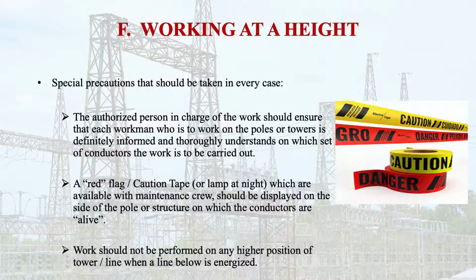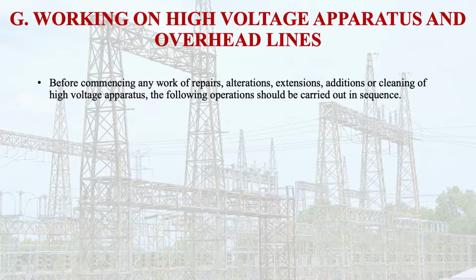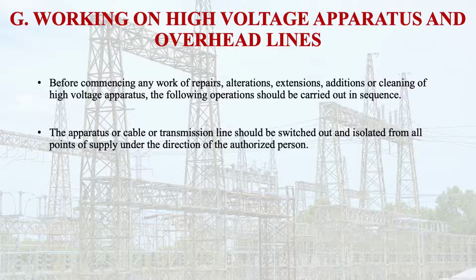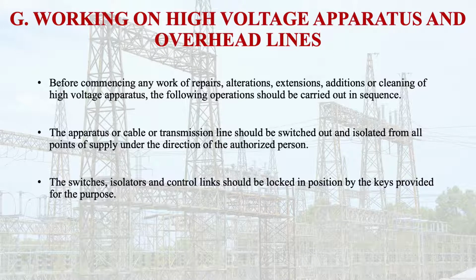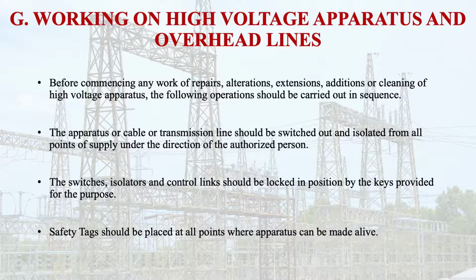Now let us discuss working on high voltage apparatus and overhead lines. What are the safety instructions associated with this? Work on the high voltage apparatus first. Before commencing any work of repair, alterations, extensions, additions or cleaning of high voltage apparatus, some operations should be carried out in sequence. What are these? Number 1: the apparatus or the cable or transmission line should be switched out and isolated from all points of supply under the direction of the authorized person. Number 2: the switches, isolators and control links should be locked in position and by the keys provided for this purpose. Then safety tags should be placed at all points where apparatus can be made alive. It is essential.